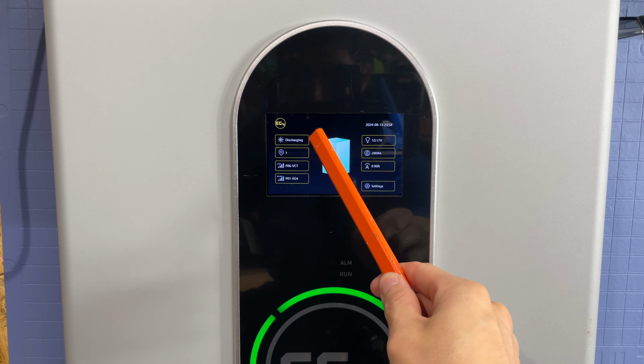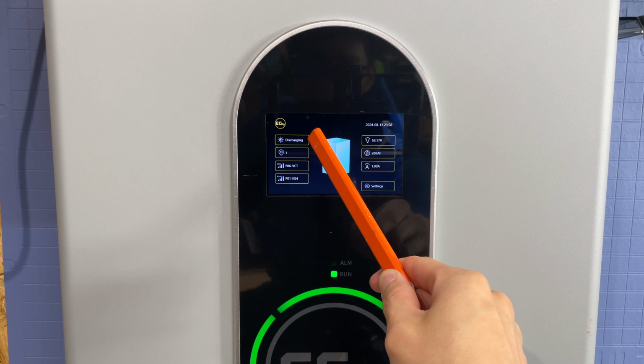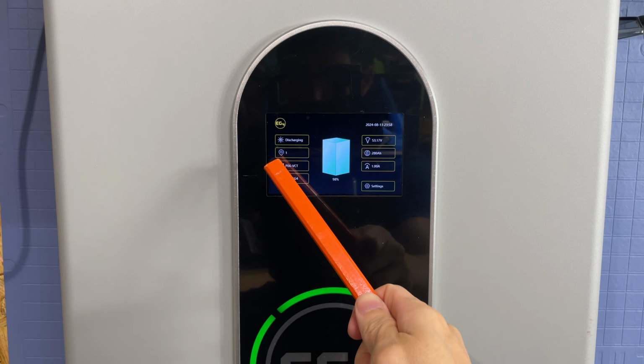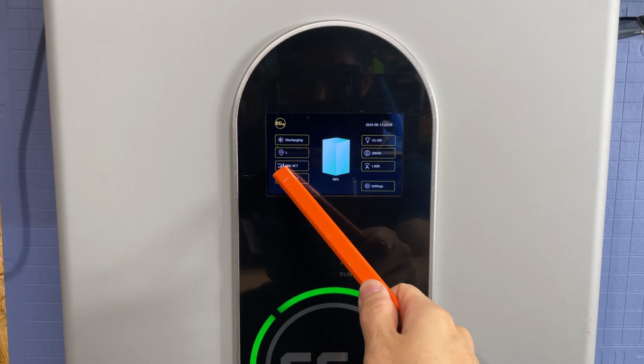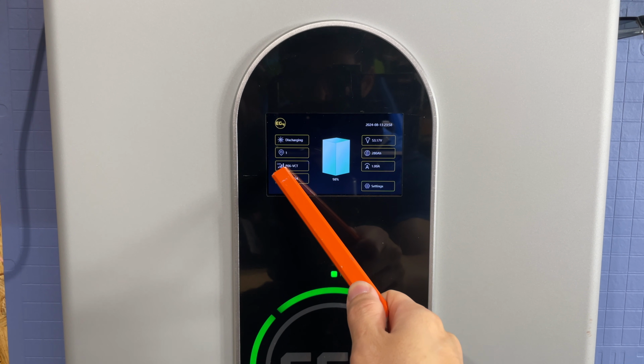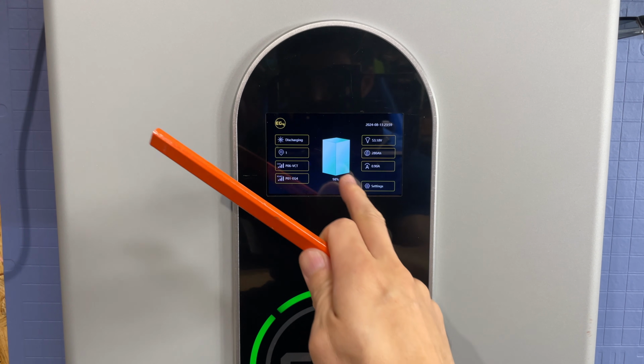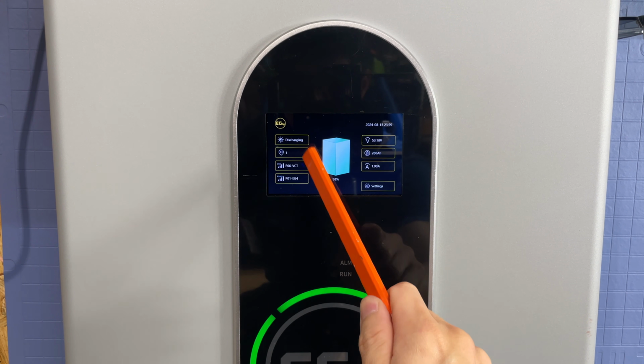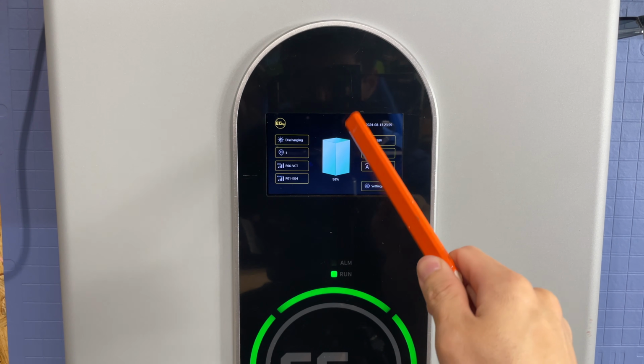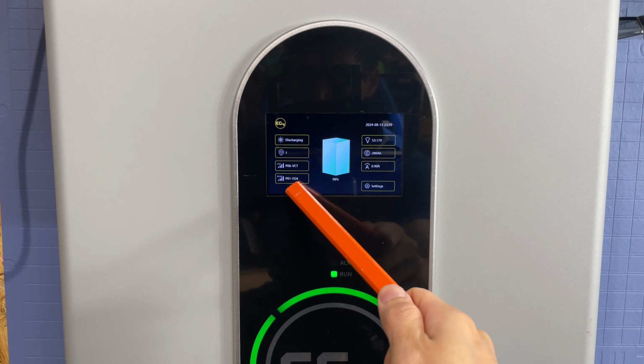As you can see, this is also a touch screen. It'll tell you the state it's in, whether it's discharging or charging. The address I have set is 1, and right now I have the CAN protocol communications set to P06, which is Victron — that's how we got the BMS communications working. This right here is the protocol you'd set if you're using RS485, which you're not using.